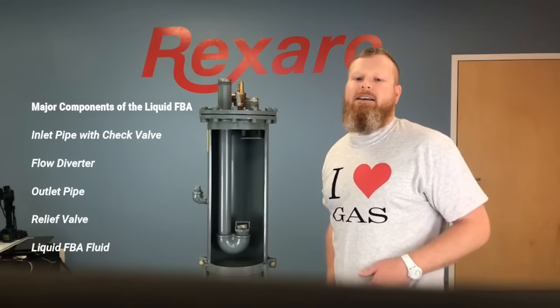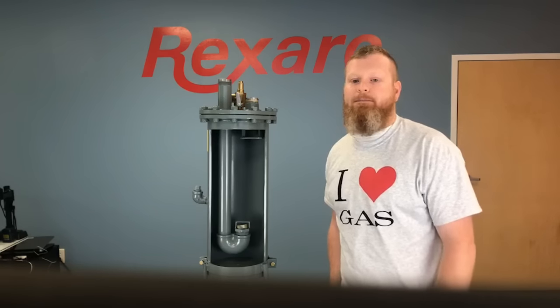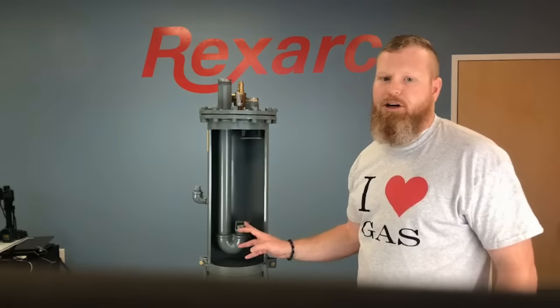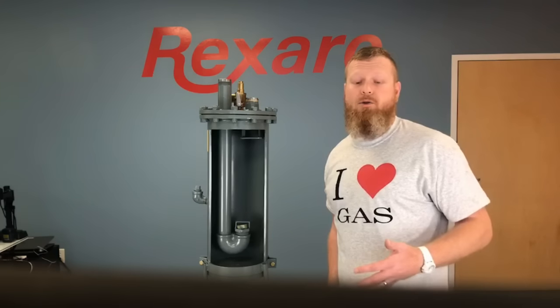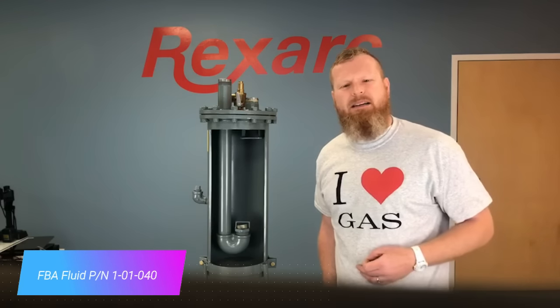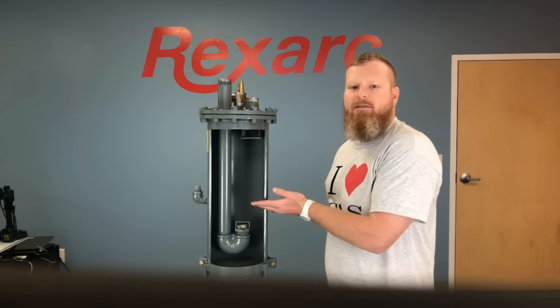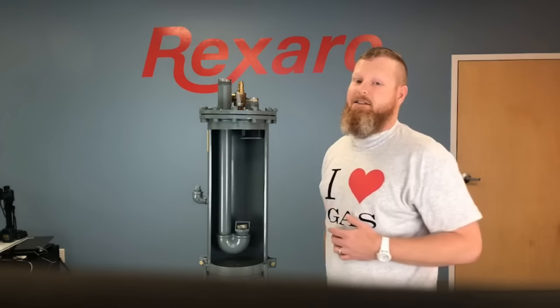Now let's follow the flow of gas through a liquid flashback arrestor to discover what each of those components does and how they function when a flashback occurs. The gas enters the flashback through this pipe at line pressure. Depending on the gas and application, this can vary between 5 and 200 psi. The most common application is for welding and that is typically between 10 and 15 psi. When the gas goes through the check valve, it also goes through the liquid flashback fluid, effectively creating a double barrier between the downstream users and the high pressure gas contained in the cylinders.